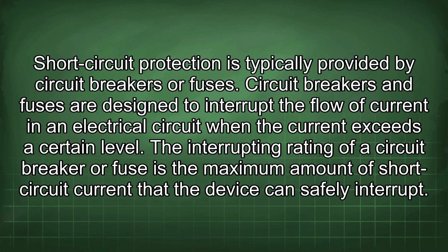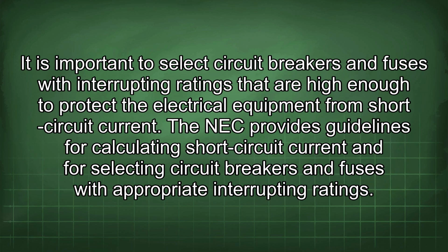Circuit breakers and fuses are designed to interrupt the flow of current in an electrical circuit when the current exceeds a certain level. The interrupting rating of a circuit breaker or fuse is the maximum amount of short-circuit current that the device can safely interrupt. It is important to select circuit breakers and fuses with interrupting ratings that are high enough to protect the electrical equipment from short-circuit current. The NEC provides guidelines for calculating short-circuit current and for selecting circuit breakers and fuses with appropriate interrupting ratings.